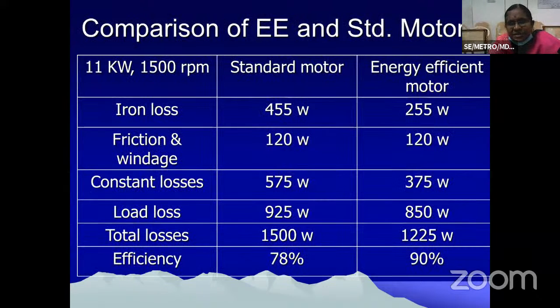So this is a comparison between the standard motor and the usage of an energy efficient motor. The efficiency of a standard motor is 78%, and the efficiency of an energy efficient motor is 90%. Total losses in a standard motor are around 1500 watts, whereas in an energy efficient motor it is 1225. So when you use motors, always prefer energy efficient motors instead of standard motors.